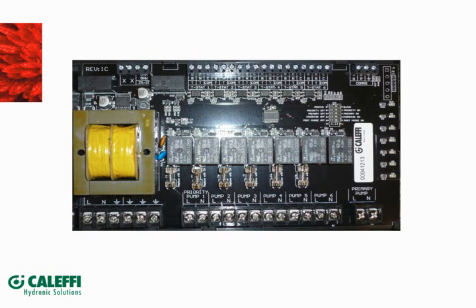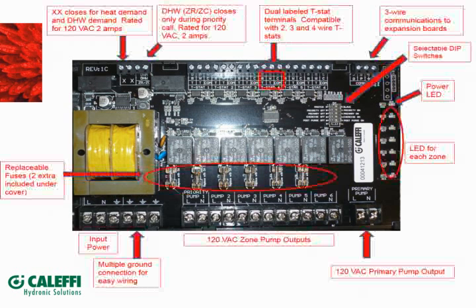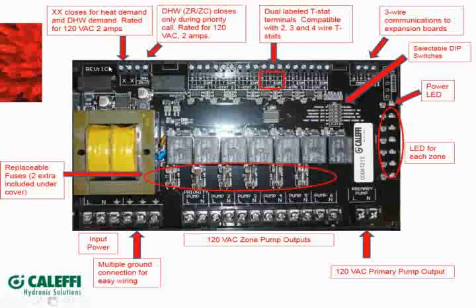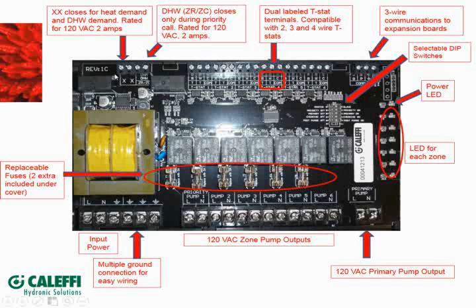Yeah. So once you pop it open, this is what the board looks like inside. Let's kind of go around the horn here. This is our end switch, and that closes on a heat demand. And it also does close when there's a domestic hot water call. Now these are smaller terminals, but they are rated for 120 volts, 2 amps. They have the proper spacing, and the board traces are spaced apart enough that we do have 120 volt capacity up here. As well as this is our domestic hot water contacts.